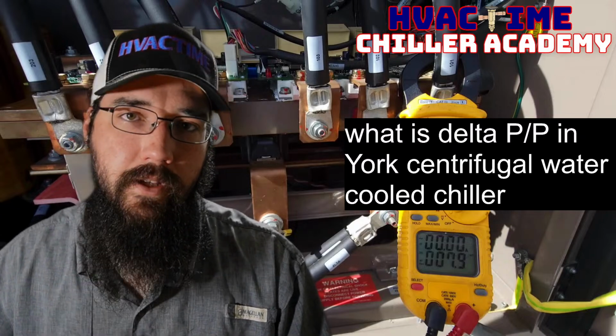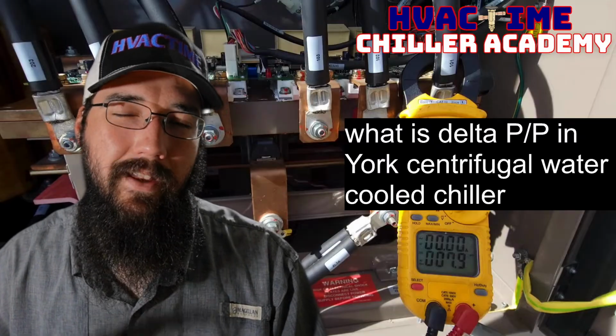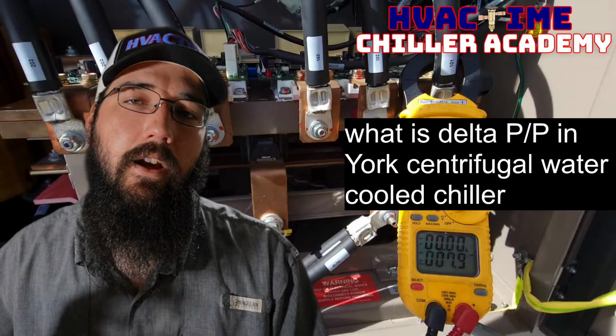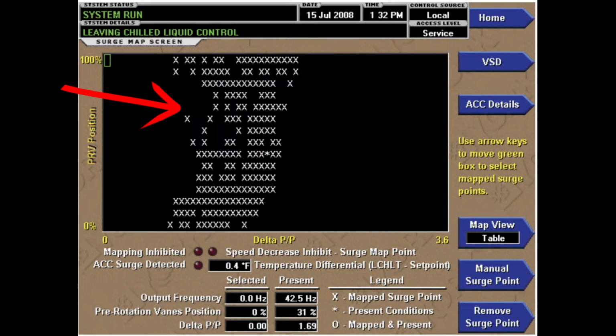So in that case, all those points now become a roadblock that isn't actually supposed to be there. Under normal conditions, some of these may not be points that would actually surge. Like this here may not be an actual surging point. This point may have graphed strictly because we had a condenser water problem.